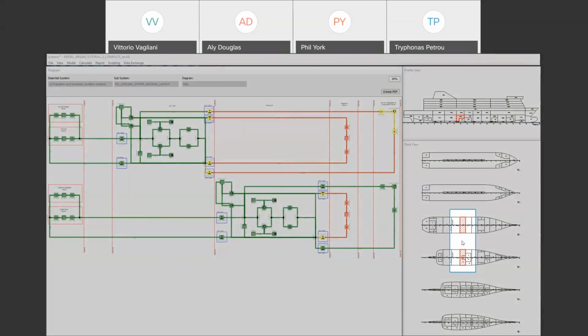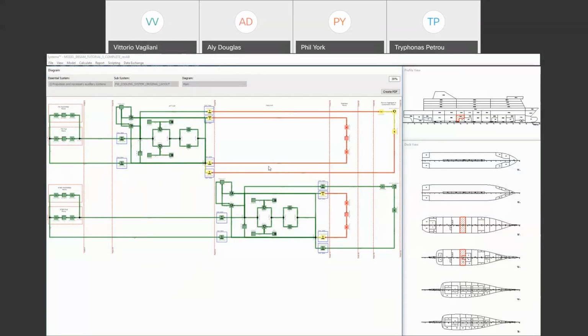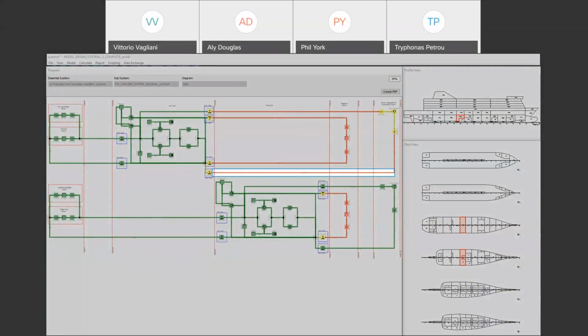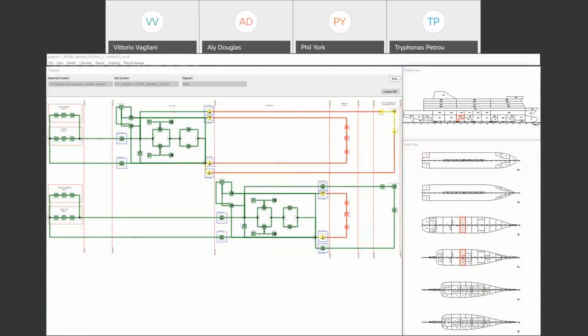For the stabilizer room loss due to fire or flooding, Systema identifies the loss of functionalities and calculates which valves have to close to contain the damage and prevent circuit depressurization. Due to pipe routing patterns, 2 additional isolating valves in the aft engine room will close. This will result in loss of air compressor's functionality as highlighted in yellow. To avoid that, both supply and return lines of compressor unit 1 should be designed to withstand the impact of the hydrostatic pressure similar to the pod unit return lines.